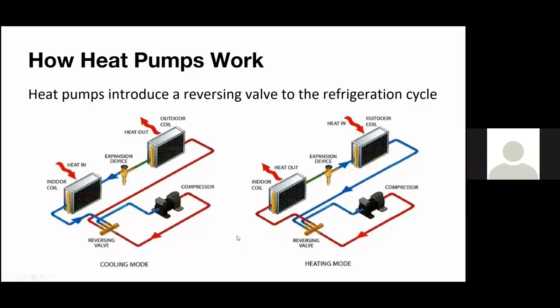So that's how you can differentiate between a cooling only air conditioner and a heat pump. They all have those basic four components: a compressor, condenser coil, evaporator coil, and expansion device. The one component that heat pumps have versus cooling only units, whether it's an air conditioner, mini split, or VRF, is that reversing valve. You need that component, that gearbox, to be able to switch back and forth between heating inside or cooling inside.